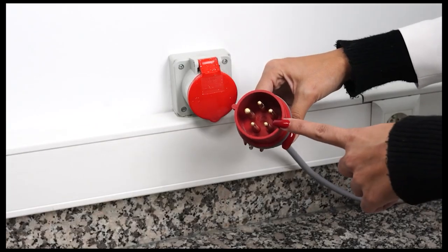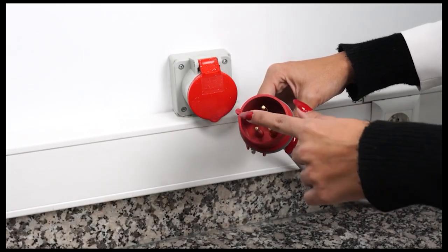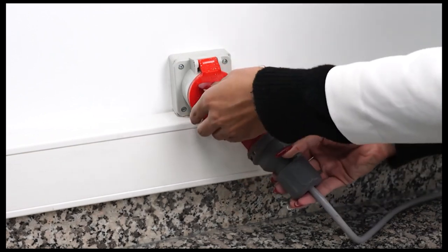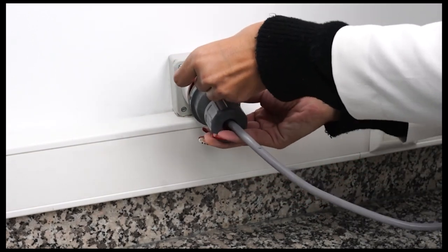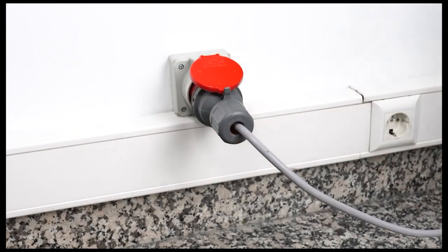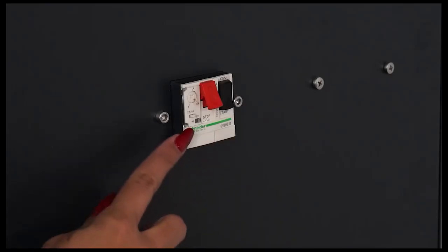After the mentioned controls of the laboratory where the device will be installed are conducted, the power cable is plugged into a grounded socket with a voltage of 380 volts and a frequency of 50 Hz. Care should be taken to have dry hands during this process. The fuse box on the back of the device protects it from high voltage and current fluctuations.